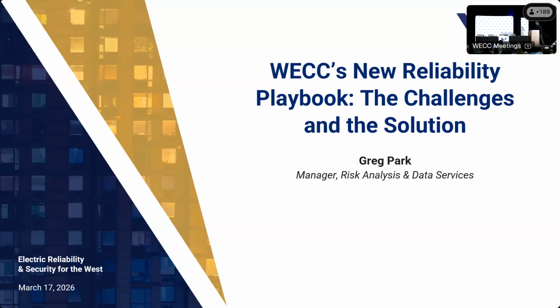So what happened in 1996 is really what I'm passionate about. The Western Interconnection broke up into many islands almost three times that summer. I was a plant operator at Sierra Pacific Power Company, NV Energy, at that time, and I learned what governor droop and deadband was. Sierra Pacific was part of one of the 5 islands that formed, and we never lost a unit due to overspeed or any plant protection. We didn't drop 1 unit, but we experienced under frequency about 5 times each one of those days. So as a plant operator, you really get to understand what governor droop is, what frequency response is. It was really a formative time in my life.